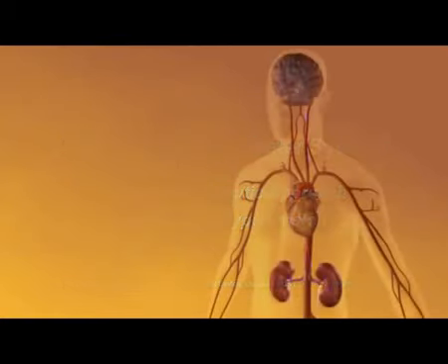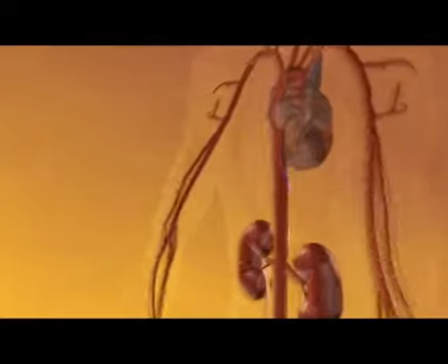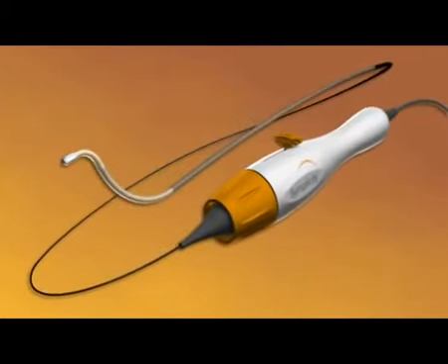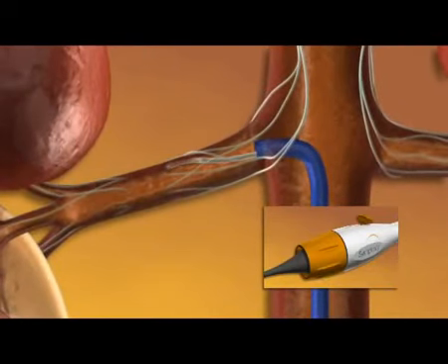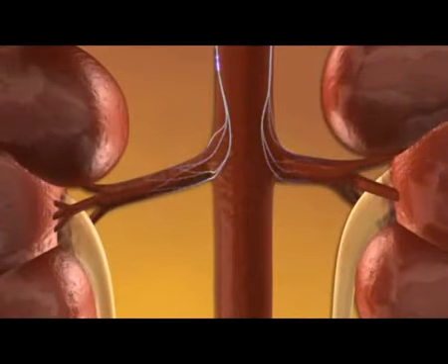The link between hypertension and hyperactivation of the sympathetic nervous system is well established. Renal sympathetic nerve signals — both those going into the kidney and those originating from the kidney — play a key role in driving this hyperactivation. The Ardian Simplicity Catheter System offers physicians a way to precisely target and deactivate renal nerves with controlled low-power RF energy delivered from the catheter tip through the artery walls to the surrounding renal nerves, intended to reduce sympathetic nervous system hyperactivity and lower blood pressure.